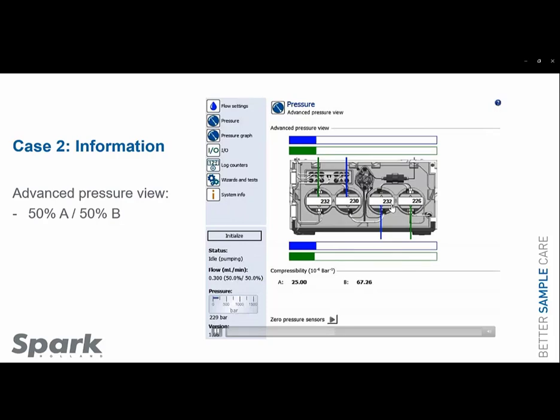Here we see that the primary pump head is 6 bar below the secondary pump head, but we also notice that the primary pump head of pump A is exactly the same as the system pressure. That's not good. This means that the system pressure is transformed to the primary pump head.